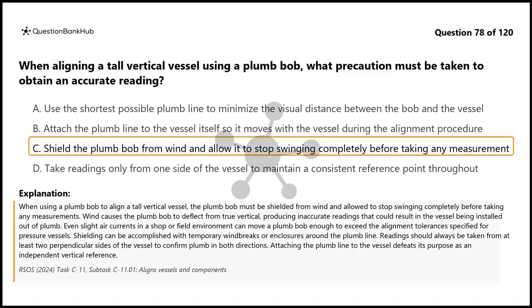Shielding can be accomplished with temporary windbreaks or enclosures around the plumb line. Readings should always be taken from at least two perpendicular sides of the vessel to confirm plumb in both directions. Attaching the plumb line to the vessel defeats its purpose as an independent vertical reference.